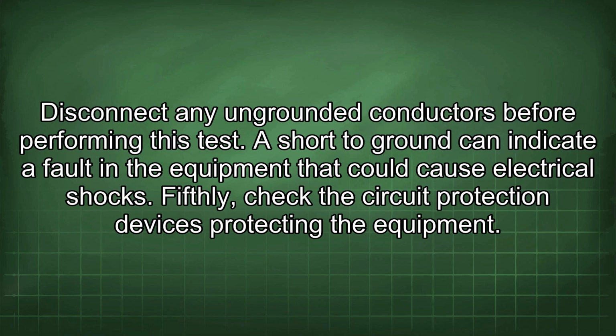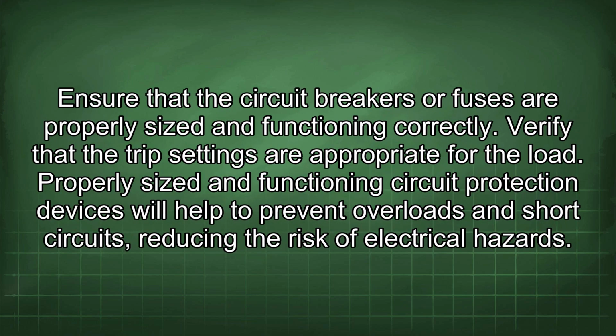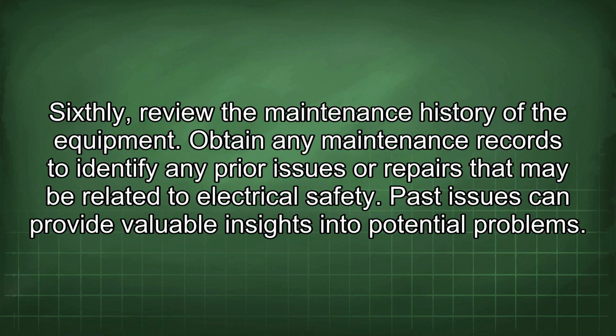Fifthly, check the circuit protection devices protecting the equipment. Ensure that the circuit breakers or fuses are properly sized and functioning correctly. Verify that the trip settings are appropriate for the load. Properly sized and functioning circuit protection devices will help to prevent overloads and short circuits, reducing the risk of electrical hazards. Sixthly, review the maintenance history of the equipment. Obtain any maintenance records to identify any prior issues or repairs that may be related to electrical safety. Past issues can provide valuable insights into potential problems.